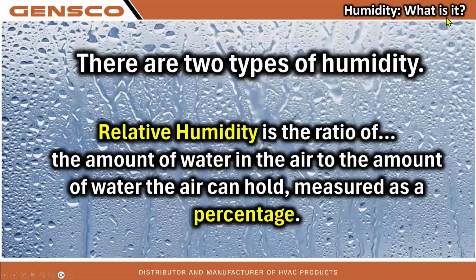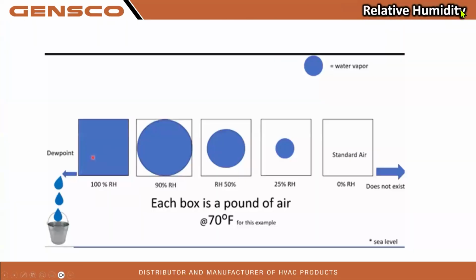Not that we're putting too big of an AC in, we just don't have a load, because we're putting in AC that's basically sized off the heat pump, the heating side. So relative humidity, everyone is pretty familiar with, you and your customers are familiar with, and we talk about it all the time. Again, that's a ratio of the amount of water in the air to the amount the air can hold. One example would be these images where we get to 100% humidity and all we need is a little bit more and we're going to start having condensation. At 90% humidity, it's very muggy. It's how much the air can hold versus how much is in the air.